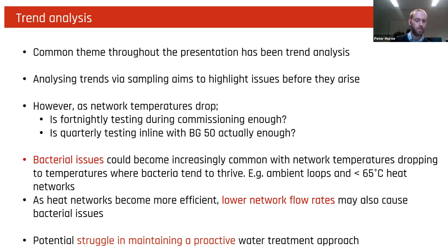So a common theme throughout this has been trend analysis, which is what we look for to highlight issues before they arise. However, I want to highlight that as network temperatures are likely to reduce, through ambient loops or heat networks becoming more and more efficient as we look to decarbonize heat, we might get to a point where bacterial issues start to proliferate at a much quicker rate. Fortnightly testing during pre-commissioning, although it might be good enough now, may not be good enough in the future. The same goes for quarterly testing for BG50. It may make this proactive approach that we're trying to adopt a bit too slow and turn it into a reactive approach, which we obviously don't want.